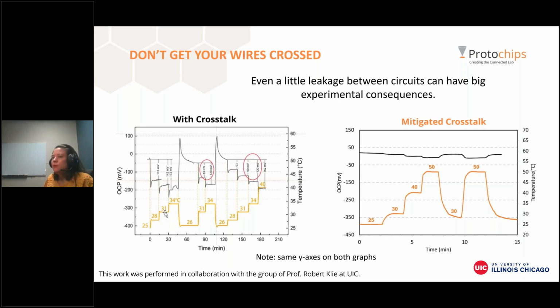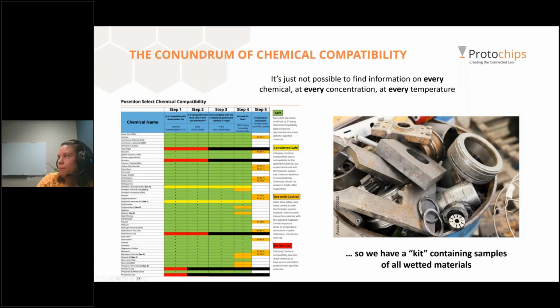So even a little bit of leakage from your heating circuit into your electrochemistry circuit will cause shifts in your OCP, and thus you'll see shifts that are not induced by your reaction itself, but rather by the lack of isolation between the 2 circuits on the holder. So this was something that took us a while to run down and to correct, but we did manage to mitigate it with the Triton AX system, and made sure that this is something that you don't have to think about.